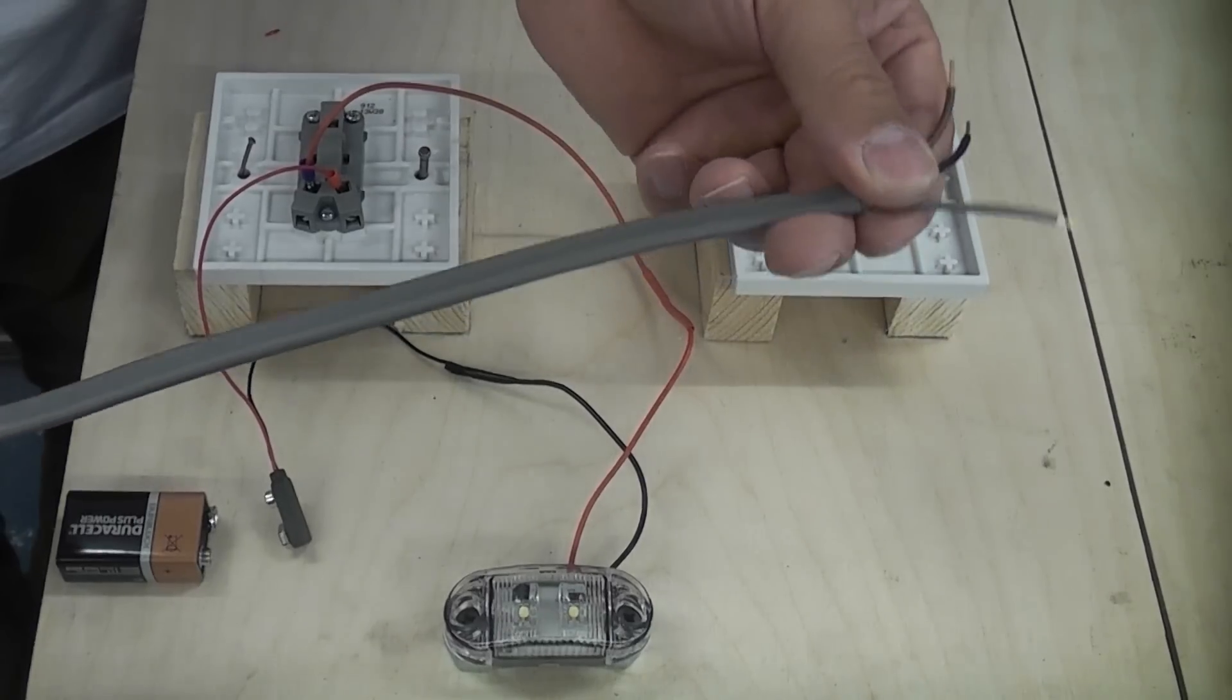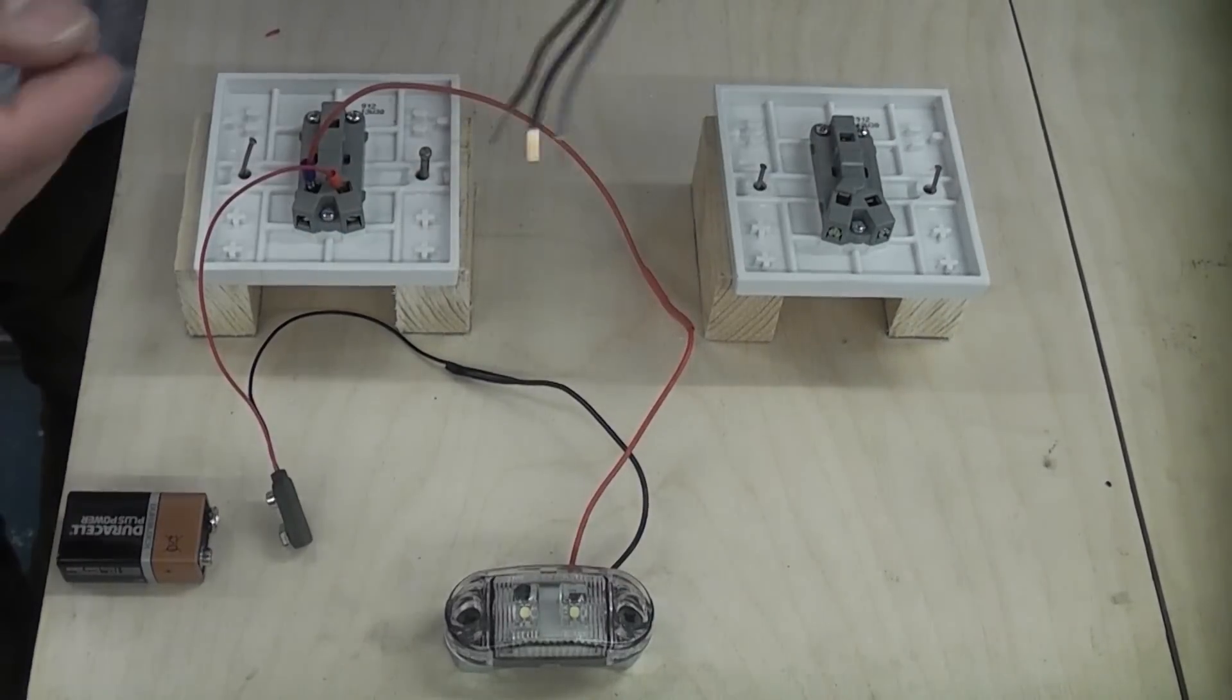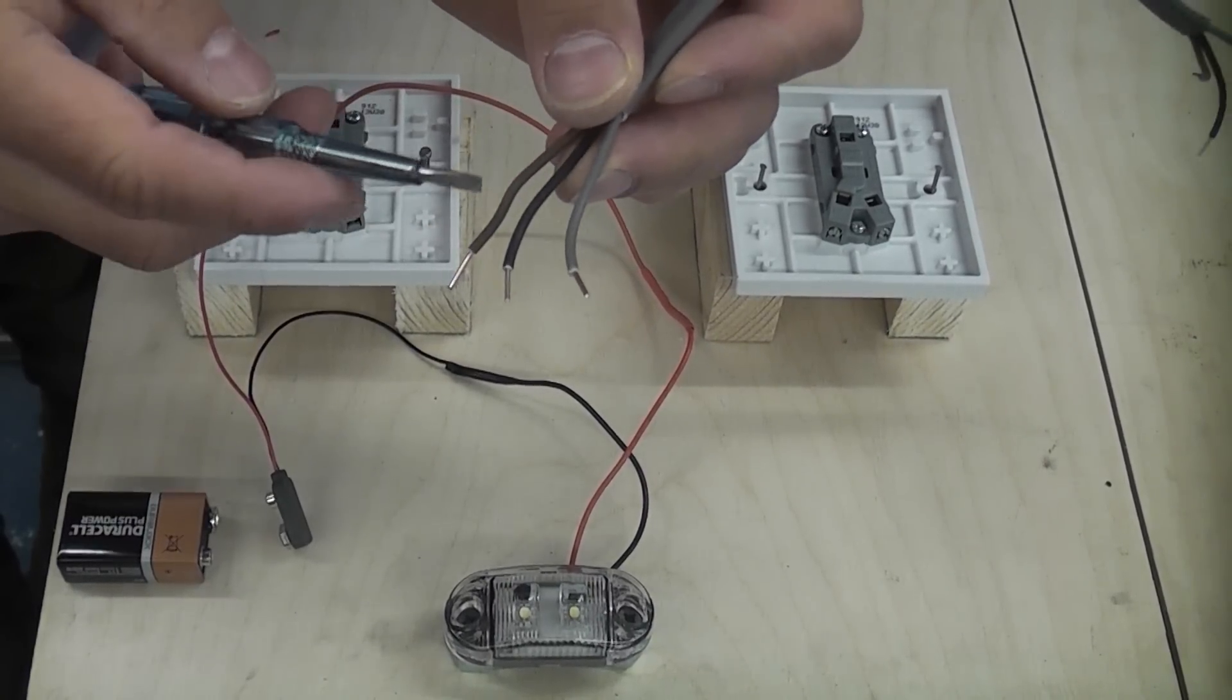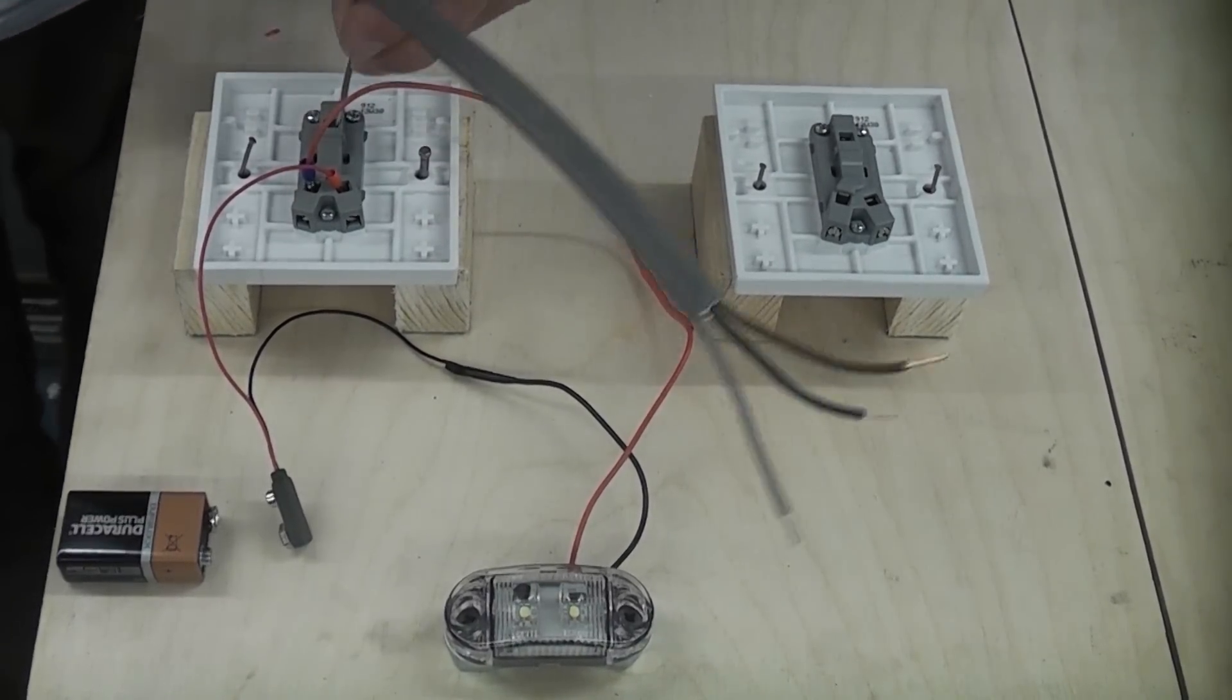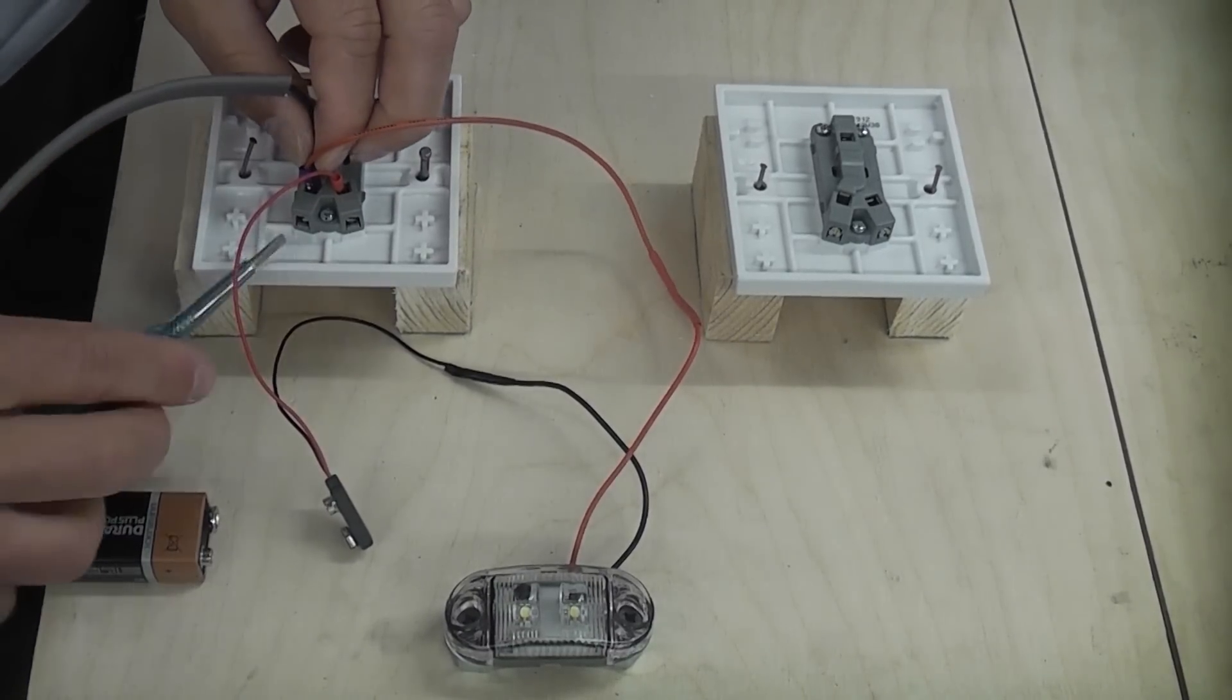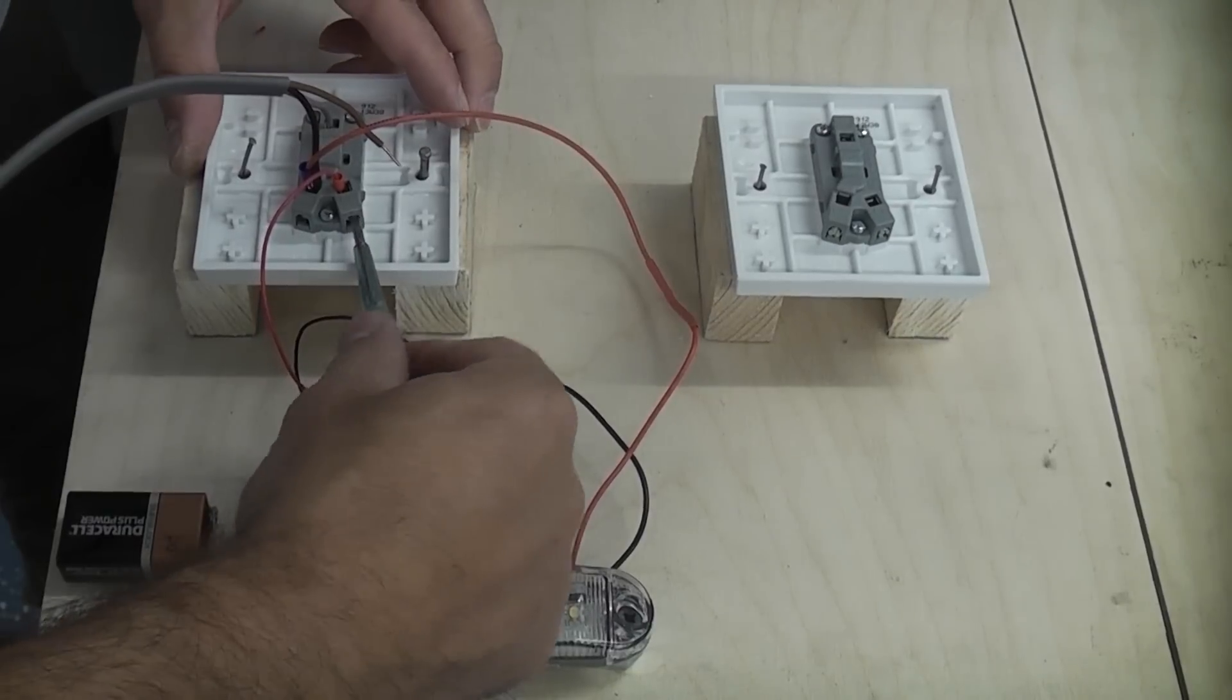Now all we need to do is get a piece of three core and earth cable. Obviously I've cut the earth off for this demonstration. You'll then notice that we have three different colors. All we need to do is choose a color. You would normally sleeve these to indicate that each one of these wires will be live at some point. So we're going to take the gray, I'm going to put that in the comm terminal. I'm then going to take the black and I'm going to put that in the L2 terminal with the other wire there.